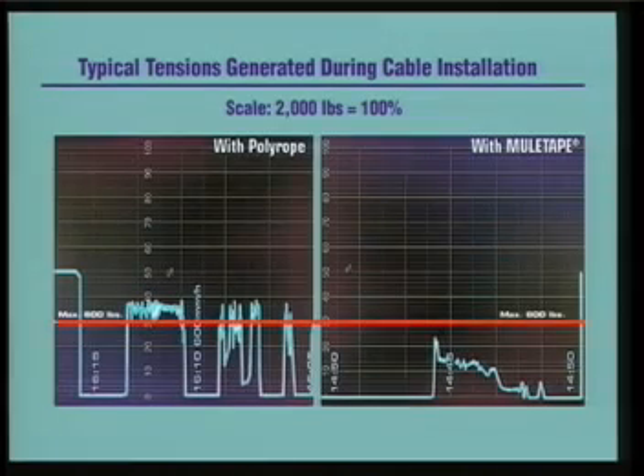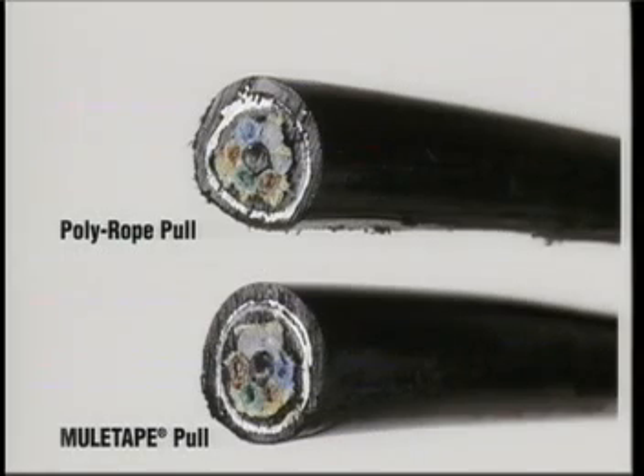The cable pulled with Muletape showed virtually no damage to the jacket or cable core. The cable pulled with polyrope, however, showed signs of severe wear on the jacket and major changes to the shape and size of the core.